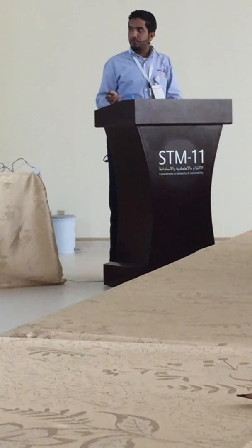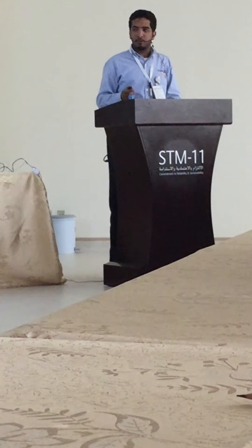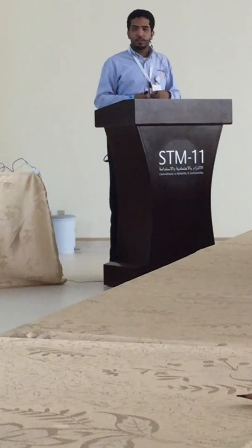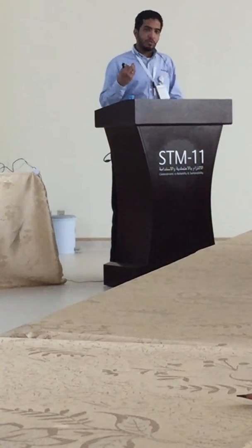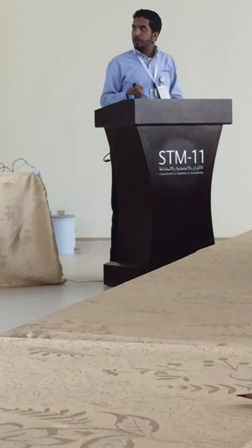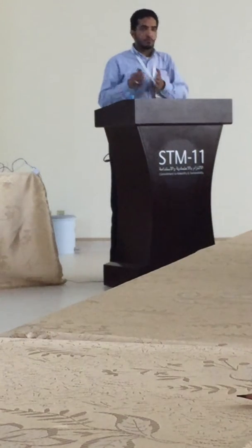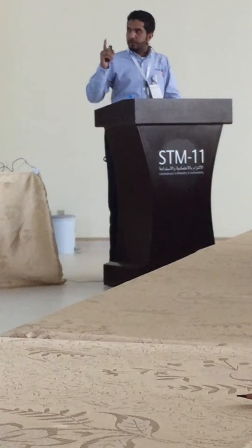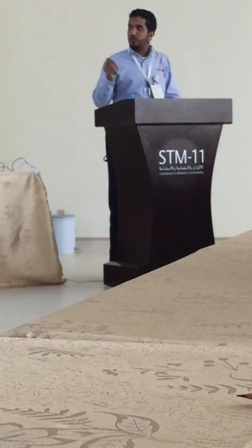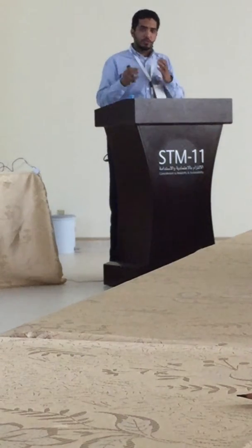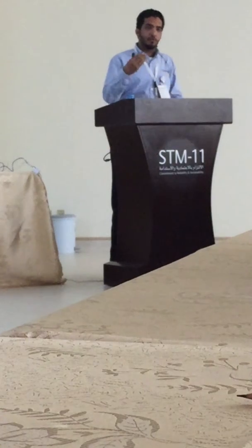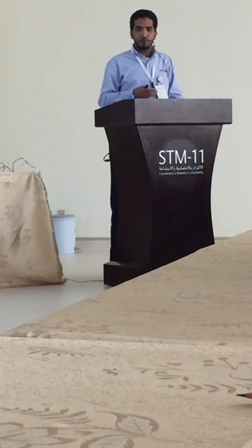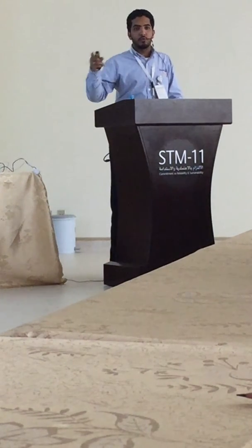Fourth step is performance tuning. We did the study for a number of cycles and we gained three more benefits. The first one is we know the limitations of our system. We know the areas where we cannot operate. Also, from cycle to cycle, we improved the accuracy of this tool. Besides these two advantages, we have one more: by changing some of the operational philosophy, we can know the change of the HTC. If we change temperature, or change the amount of ethylene to the reactor or the amount of solvent, what will be the impact on the HTC?